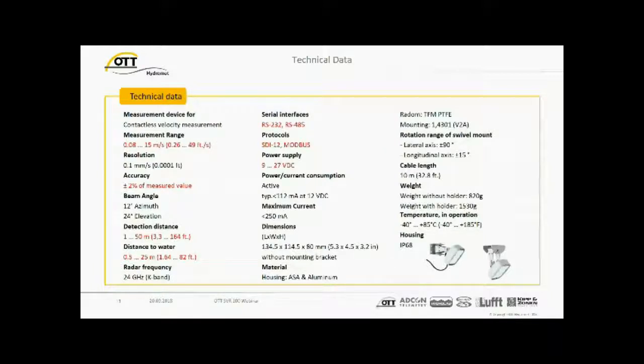Technical data in an overview here, we talked about distance already. The detection distance is 1 to 50 meters, which is the length of the radar beam finally. The vertical distance from the installation point to the water surface is a minimum of 0.5 meters up to 25 meters. We are operating in a radar frequency band of 24 gigahertz, K-band.